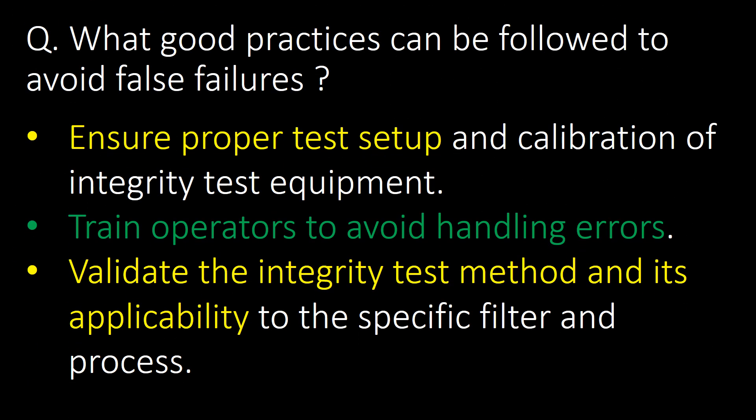What good practices can be followed to avoid false failures? Ensure proper test setup and calibration of the integrity test equipment. Train operators to avoid handling errors, and validate the integrity test method and its applicability to the specific filter and process.